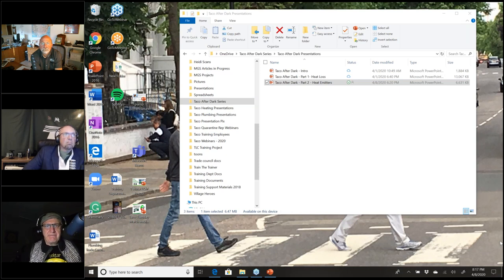Rick, you were raising your hand again. Well, no, I was just saying that's the product I have in my house. My comment is, in my particular system, I use a 30 degree delta T in my radiant floor application, because it's an above the floor remodel product that uses aluminum, and I don't have a surface temperature profile issue.